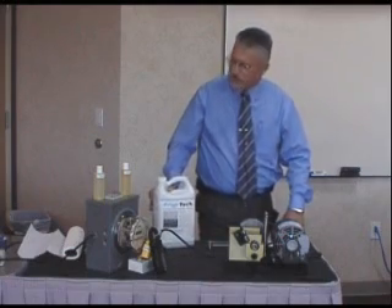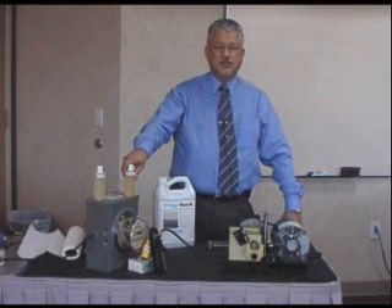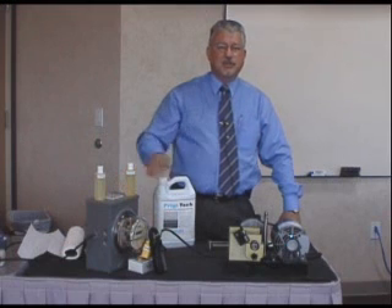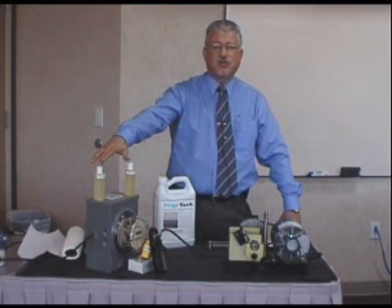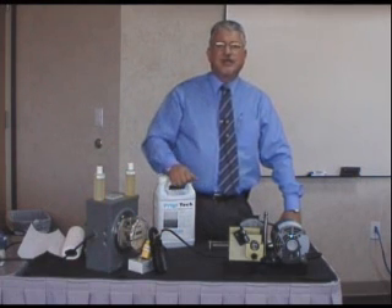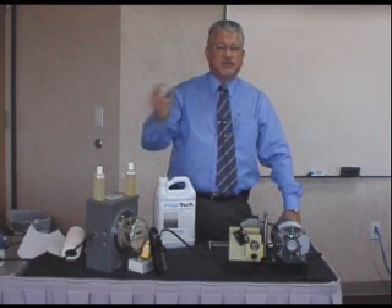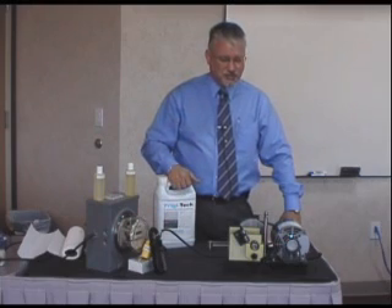I'd like to demonstrate it for you and compare Suniso 3GS, which is the industrial standard lubricant used in air conditioning systems in the United States, then add FrigTech to it. Color-wise they look virtually the same. FrigTech is an additive — you add it at five percent by volume on regular AC systems and about eight percent on ammonia systems. It does not replace the standard oil; it can be blended with any type of oil, whether mineral or synthetic, and works with ammonia, Freon, or even brine systems in ice arenas.